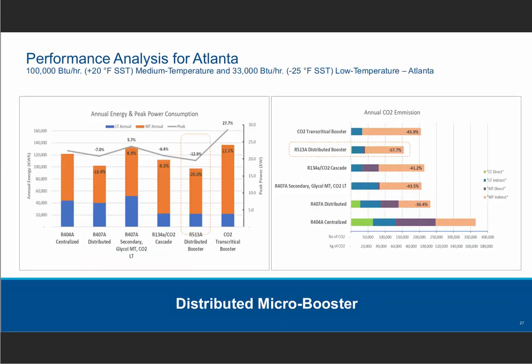And I think this may be my last chart here. It talks about the performance analysis of the micro booster for 100,000 BTU unit in Atlanta. And it compares different architectures: 404A centralized, R407A distributed, a R407A secondary with glycol, medium temp, CO2 low temp, a CO2 cascade, a micro booster, and a CO2 transcritical. And the dark blue is low temp annual energy. The orange is medium temp annual. And the gray is peak energy comparison from one system to the other.